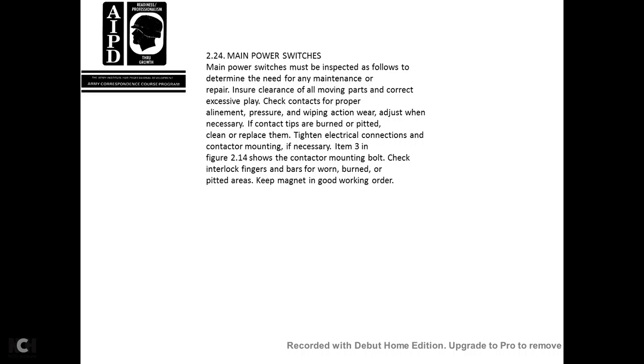224, main power switches. The main power switches must be inspected to determine the need for maintenance and repair. Insure clearance of all moving parts, correct excessive play, check the contacts for proper alignment and pressure, wiping action, wear, and adjust as necessary. If the contacts are pitted and burned, clean and replace them. Tighten all electric connections and contactor mounting as necessary.